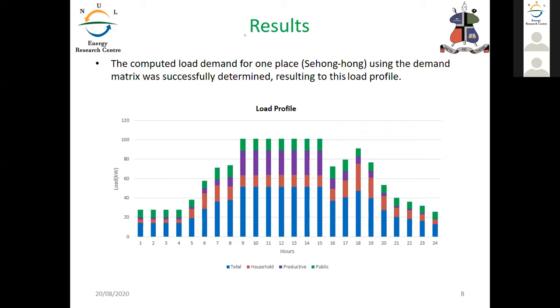From number nine, effectively doubling the consumption. I was saying the way he has portrayed it effectively doubles the consumption. Yeah, exactly. So that means the actual peak load there is 50 kilowatts, not 100. Your representation doubles whatever you have because you disaggregate over the total.